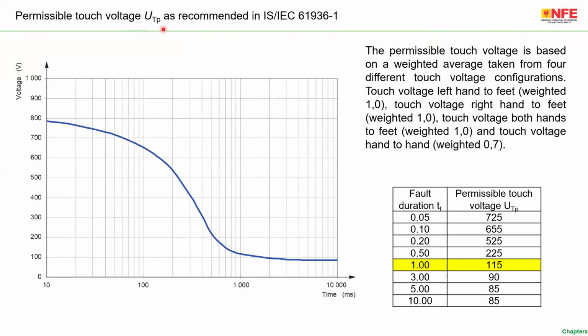Permissible touch voltage recommended in IEC 61936. This is the IEC 61936. What does this mean? If you are getting a shock from a touch voltage, either the shock intensity has to be limited to less than this particular graph, or disconnection should happen before the touch voltage crosses the limit, or so on.